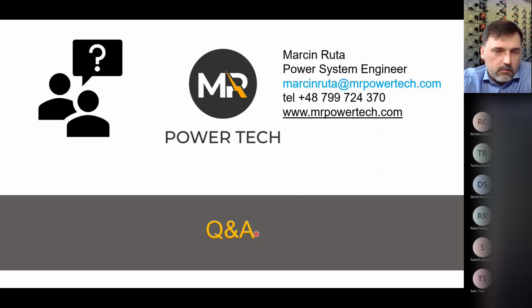But as well, 99 out of 100 low voltage switchgears will not have any arc rating, or they will be only partially rated. So let's say on the other side, you have a normal, typical low voltage switchgear, let's say 2500 amps. You are going to operate it, let's say on off, but you know that you have 40 calories, or maybe 30 calories per square centimeter energy. If you look deeper into NFPA 70E, NFPA has a very nice table called likelihood of occurrence of arc flash, and it will tell you that for normal operation, like switching on, switching off, or switching a breaker or contactor, you don't need any additional PPE if everything is in normal condition. And they state what is normal condition.